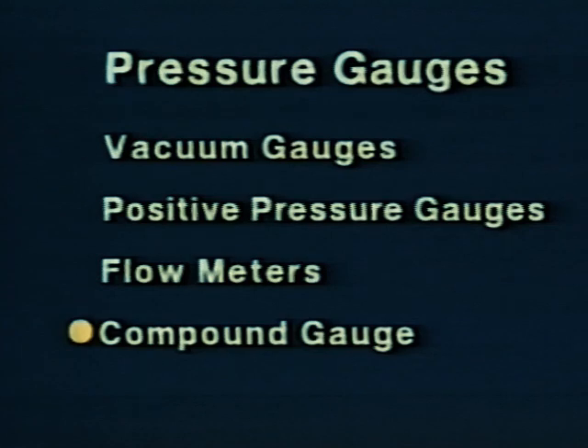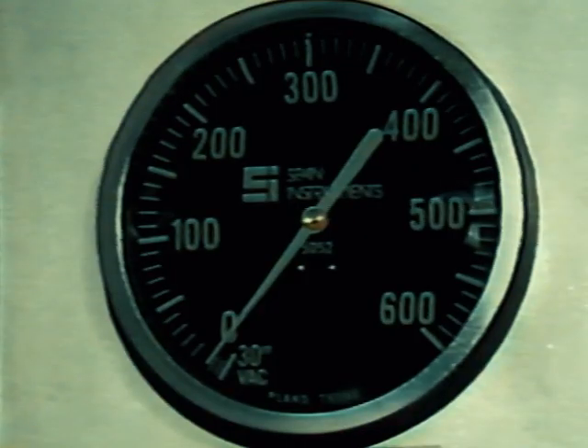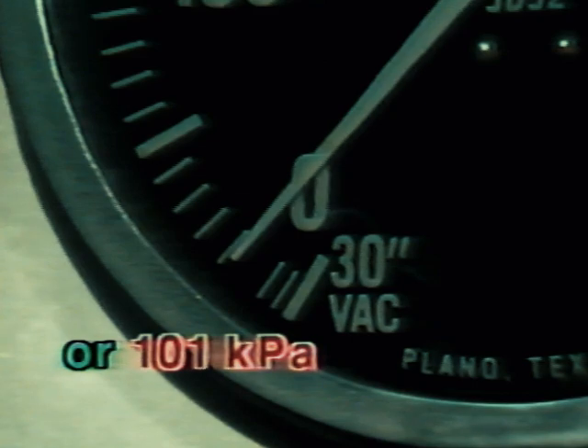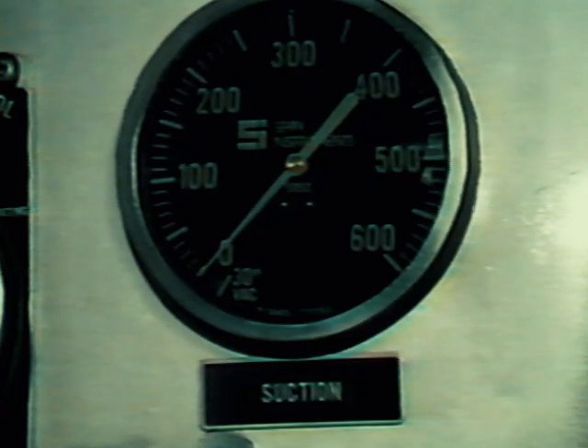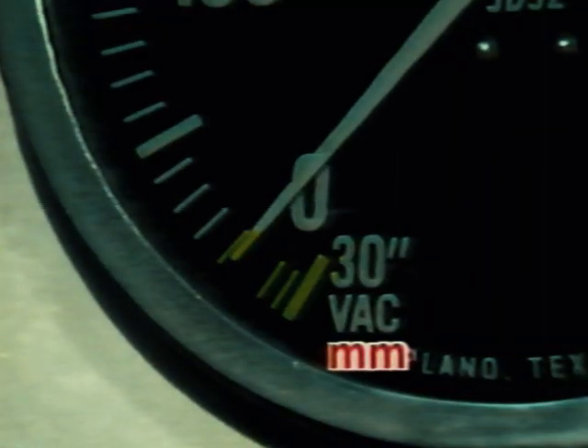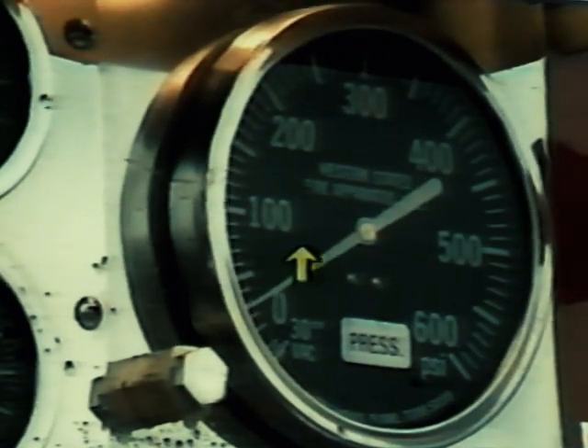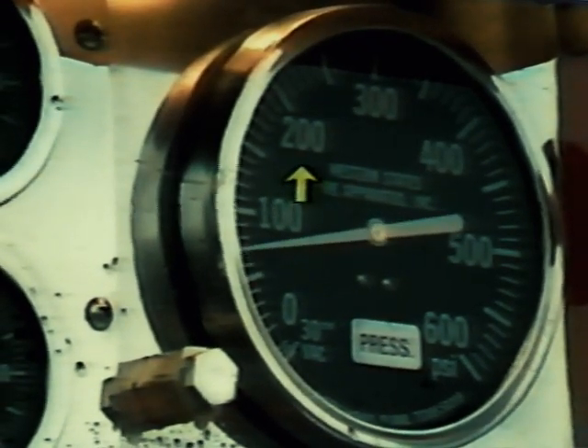The compound gauge is another gauge found on the pump panel. This gauge is designed to measure incoming pressure, both positive and negative, on the main pump. The zero on a compound gauge actually represents atmospheric pressure, or 14.7 pounds per square inch. A compound gauge is calibrated in pounds per square inch for pressures above zero, and in inches of mercury for pressures below zero. The needle of the gauge rotates clockwise for positive pressures and counterclockwise for negative pressure.